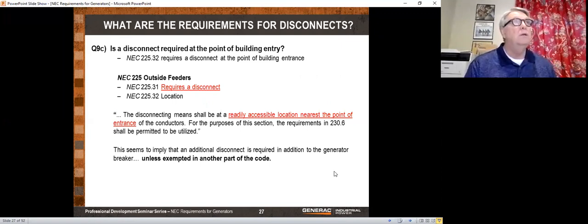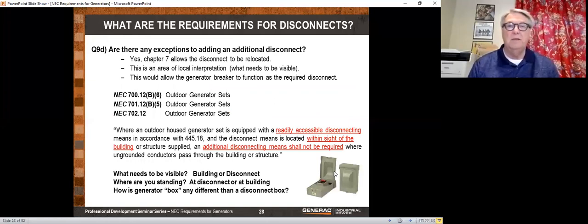Well, you generally need a disconnect whenever you have a feeder that goes into a building in order to feed power there. However, with a generator, you don't need that because it is exempted. And you can see that for outdoor generator sets, they say that when the outdoor generator set is equipped with a readily accessible disconnecting means, well, there's that circuit breaker again, and the disconnect means is located within sight of the building, an additional disconnecting means shall not be required.